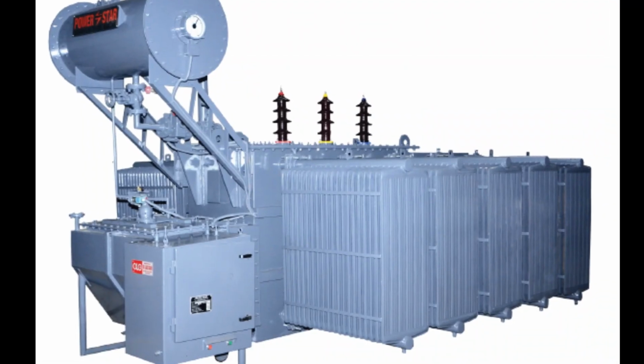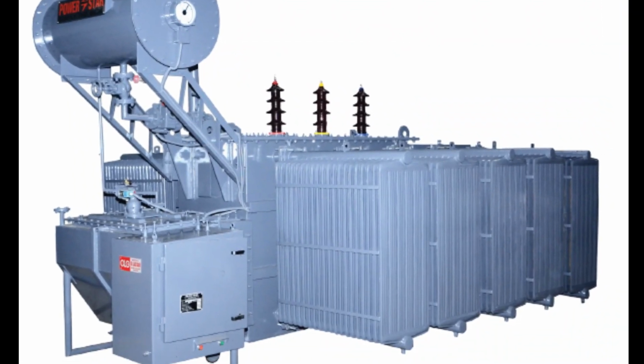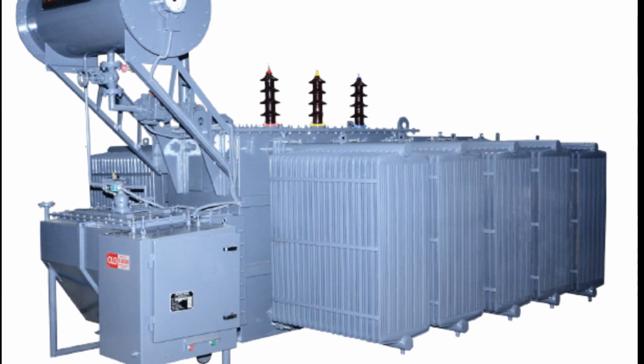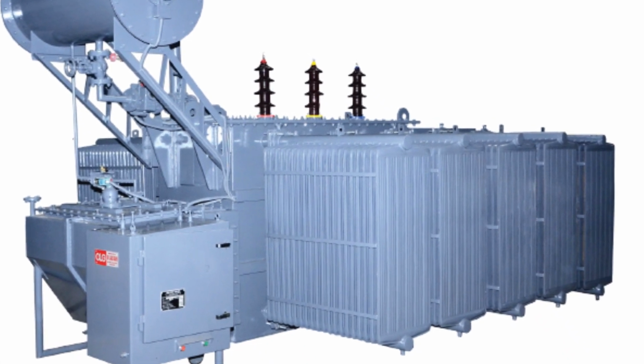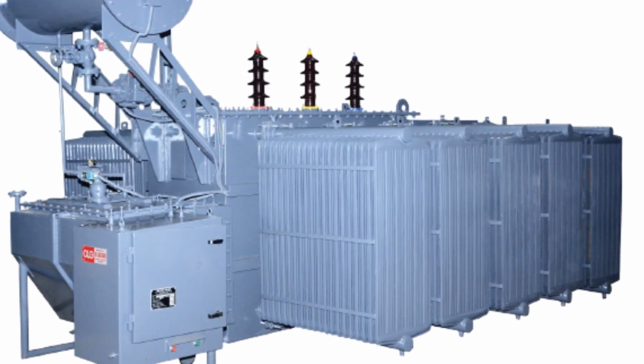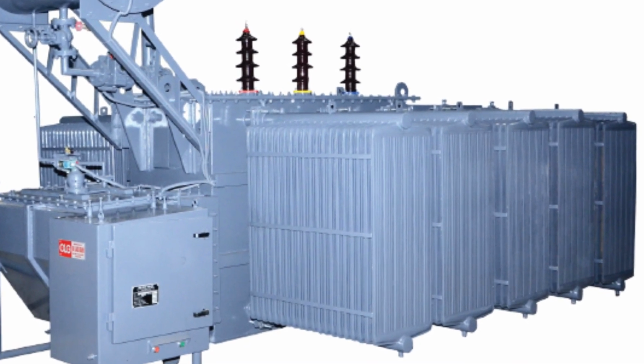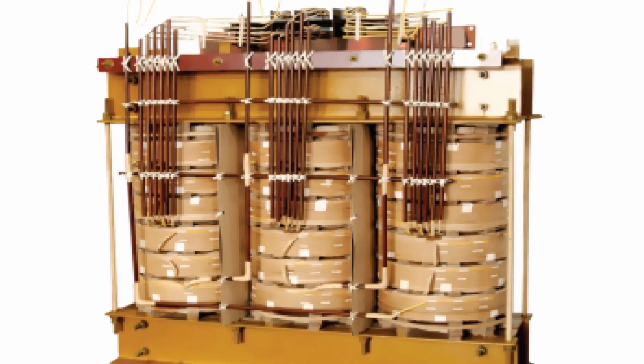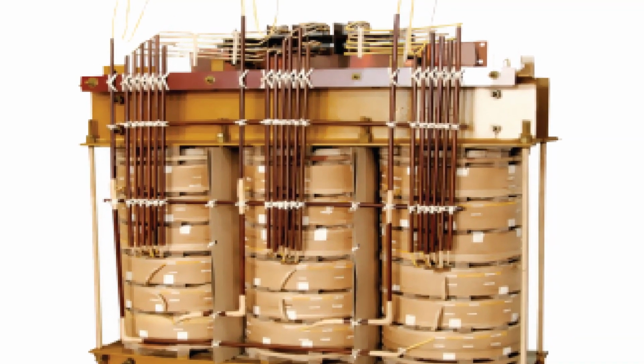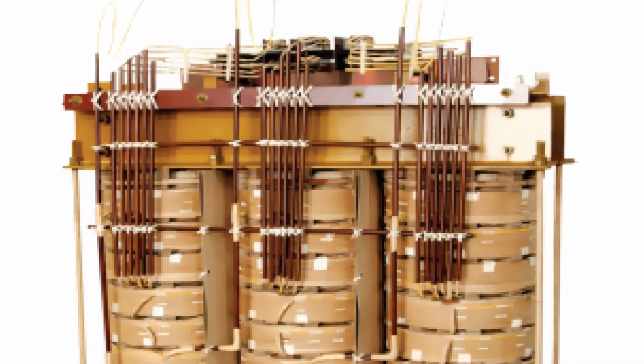Do you think derating a standard transformer is the recommended solution for high harmonic loads? Actually no, derating of transformer is not the solution. The best solution to excessive transformer heating is to replace the standard transformer with a K-rated transformer properly sized for the harmonic load.